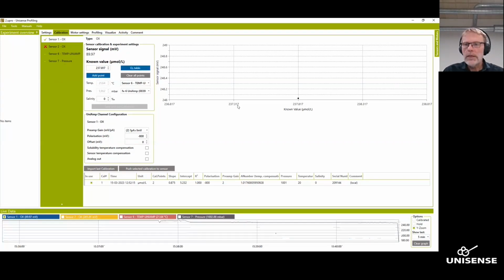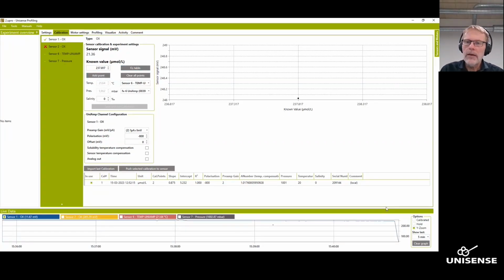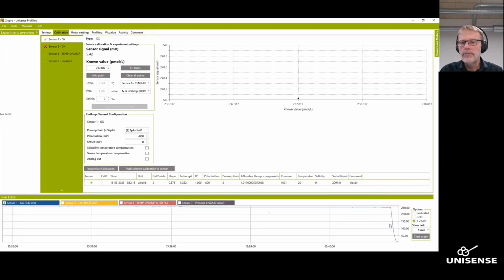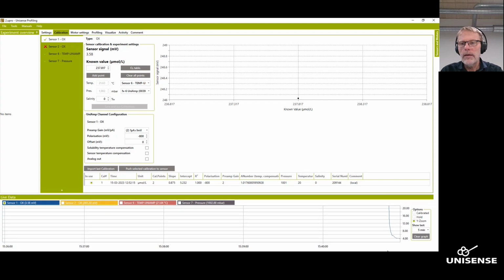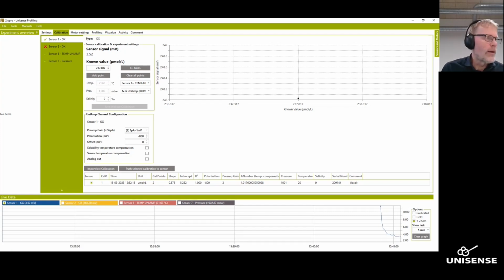I'll put the sensor in, and you will see now the signal is decreasing down here in the live view. The Y zoom is clicked, so I can just click and drag, so I can zoom in and see if it gets stable. It just takes a little while to respond. Normally, these respond within 90% respond within 5 seconds or so, maybe a little less, 3 seconds now and then. I just have to wait for a full response here, and that is about now. I think it's become stable.